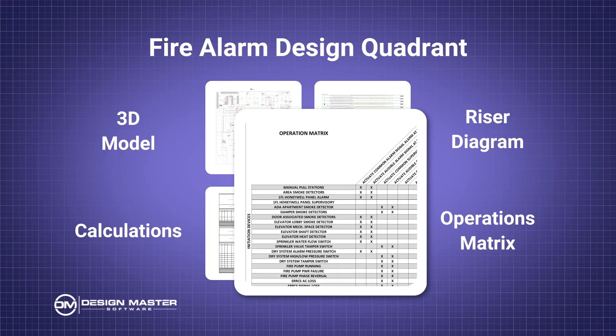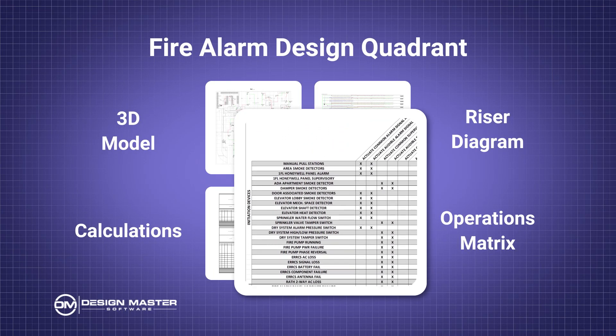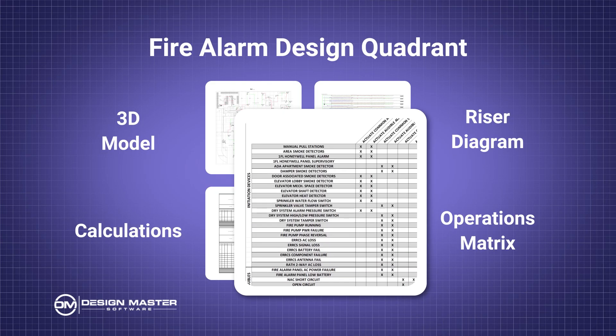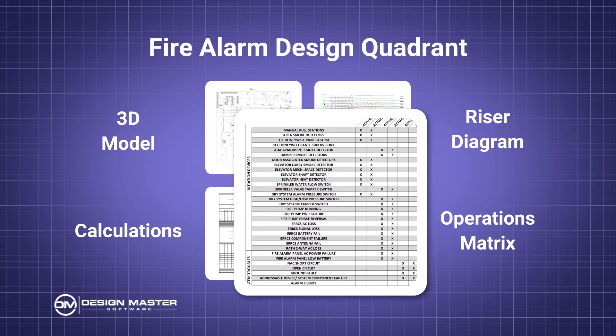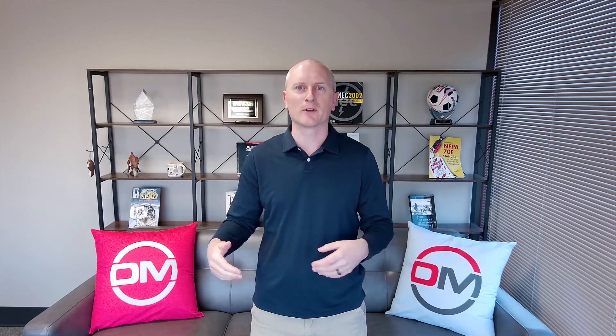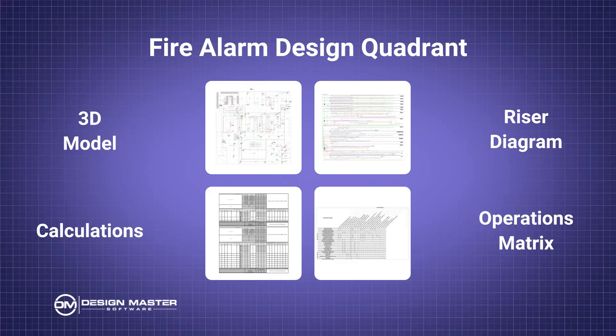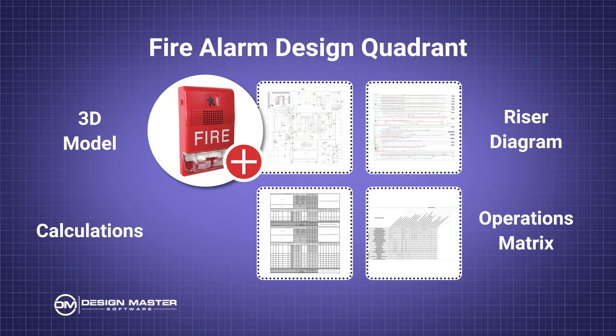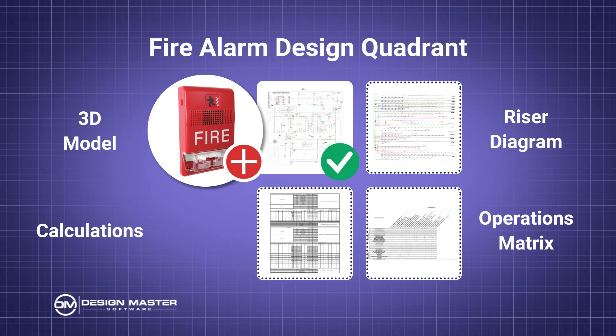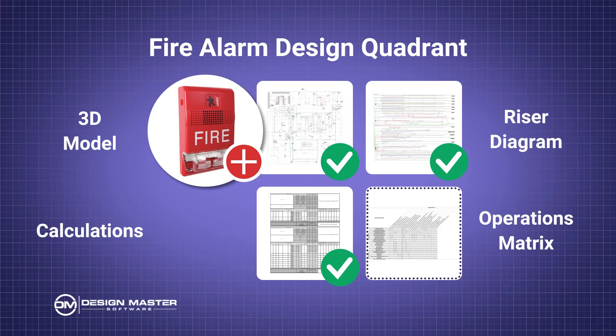The operations matrix — or input-output matrix, or whatever you call it in your designs — is the list of all of the devices that provide inputs to the fire alarm system and then all of the outputs that can happen. The list of inputs and outputs for your system is a function of the specific devices you are inserting in the design. If you add a device in your 3D model, you need to make sure it shows up in 3D and also on the floor plan. That needs to be added to the riser, included in the calculations, and if it's a new type of device, you might need to add another row or column to the operations matrix to represent that new device.